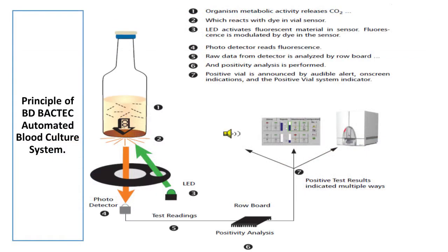The principle of the BD BACTEC automated blood culture system utilizes fluorescent technology in detecting the growth of organisms in blood culture bottles. When microorganisms are present in the cultured vials, they metabolize nutrients in the culture medium, releasing carbon dioxide into the medium.